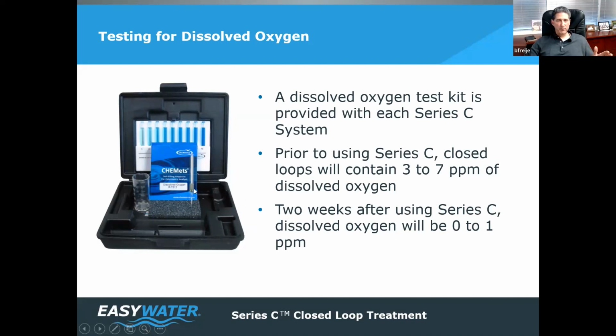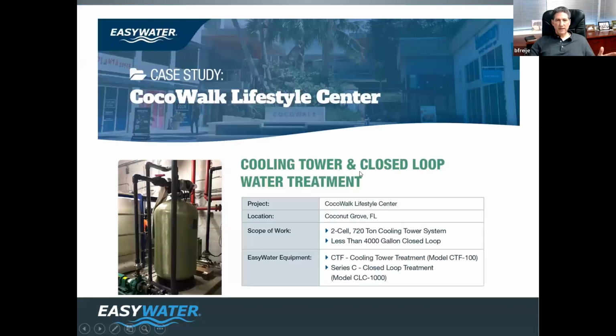The glass sample now will be clear or close to clear, meaning there's little to no dissolved oxygen now, which, as you can imagine, with little to no dissolved oxygen, that means your customer is going to have extremely low corrosion rates.